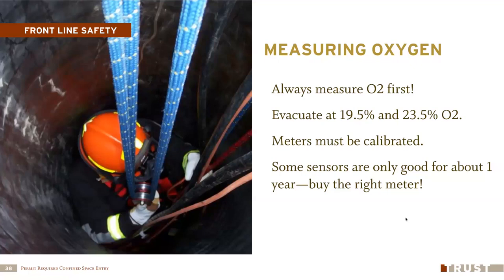We always measure oxygen first. That's essential for life, and it's also essential for some of the other sensors to work appropriately. So measure oxygen first and make sure it's within that 19.5% to 23.5% window. Realize that on these meters, sometimes sensors are only good for about a year, so as you purchase these, ask the supplier what the guarantee is on the sensors. You can buy meters with sensors guaranteed for up to 5 years, and I'd recommend that, because a year can go really quickly.